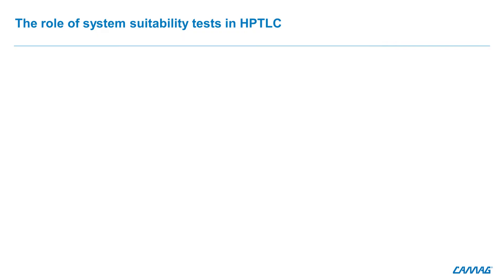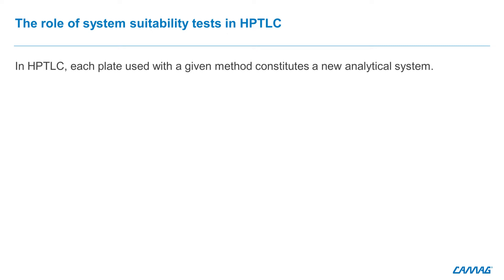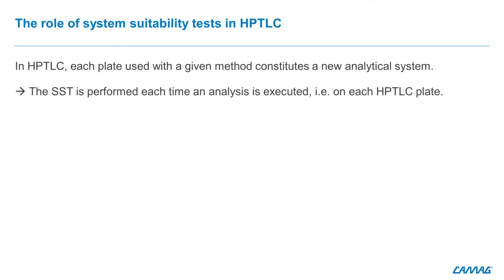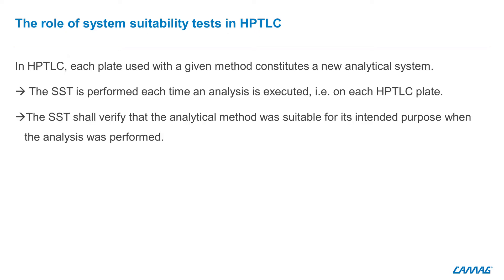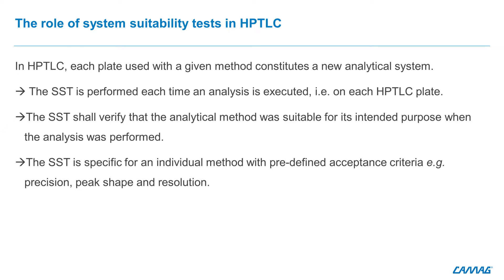What is the role of the system suitability test in HPTLC? In HPTLC, each plate represents a new analytical system. That's why the SST is performed on each plate each time an analysis is executed. The SST shall verify that the analytical method was suitable for the intended purpose the day it was performed. Until now, the SST is specific for an individual method including predefined limits.